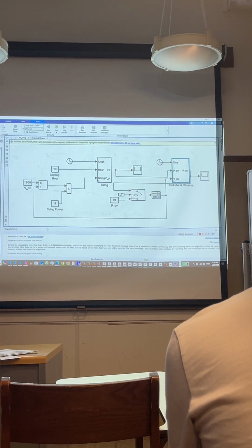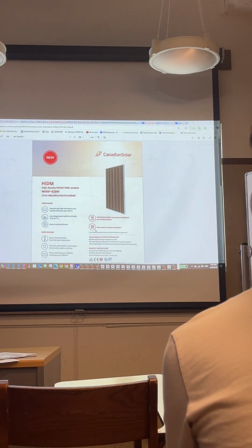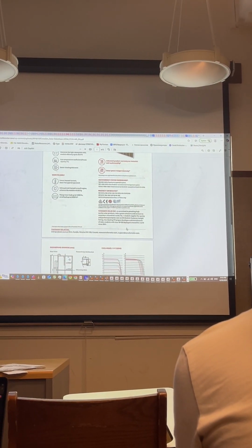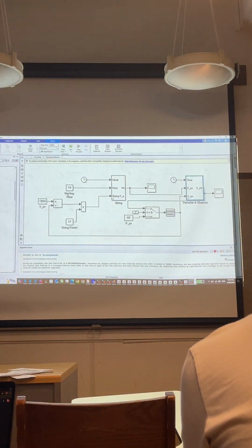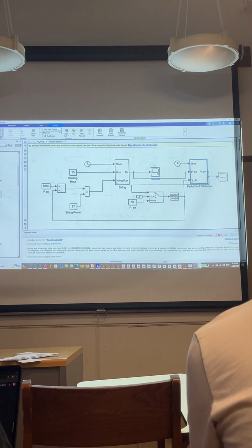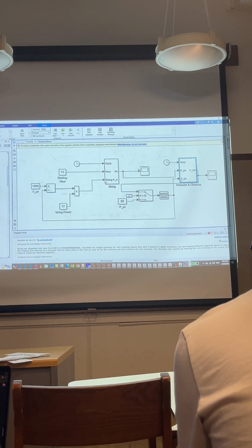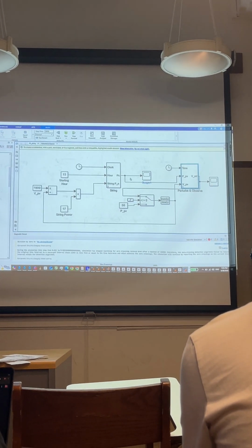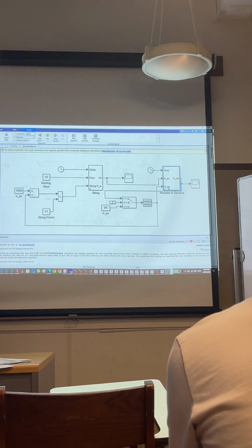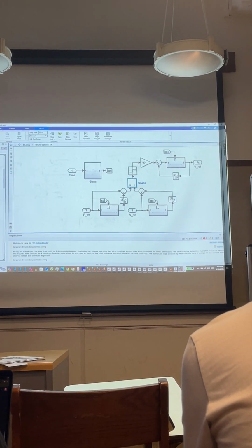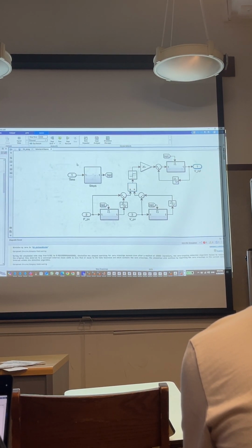So let's go back to what we started with. We have a 420, where we said 40 modules of 420 power are going to be at 1800 volts operational voltage. Okay? So the numbers are correct here. So if this power is correct and it should give the hump as we saw it earlier, this voltage here would be the desired maximum voltage, and this perturbed observed should give the proper V reference for the module.